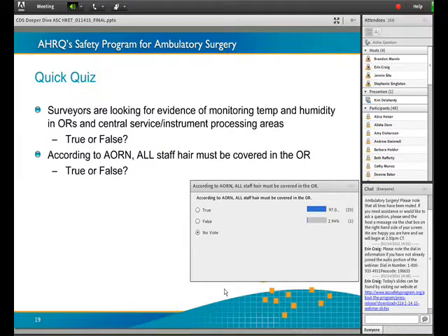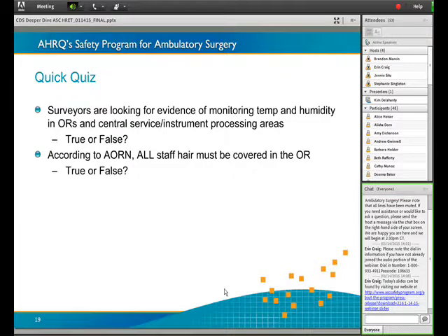Your humidity ranges need to be between 20 and 60%. The higher the humidity, the more of an infection control issue. The lower the humidity, the more of a fire risk. So it's a blended reason why you have to monitor your humidity.